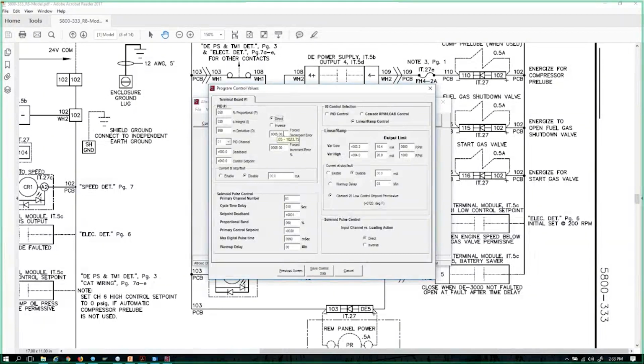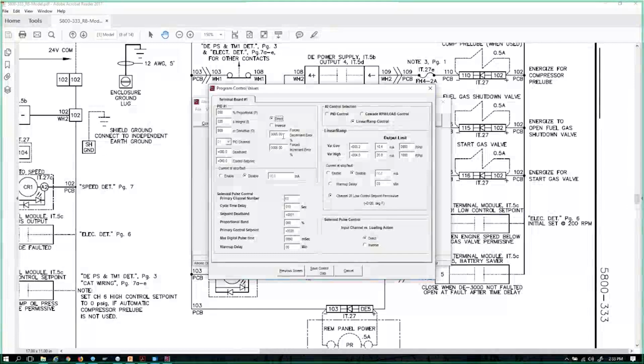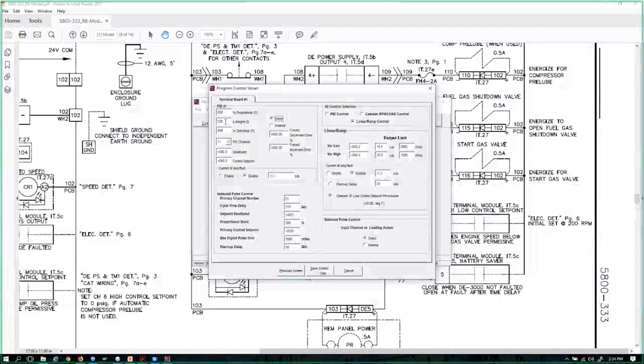I've been messing with the DE products since I think I got my hands on the very first DE product in about 2000, 2001. I've never changed these, never had a reason to. So 5% works good for me. But let's talk about proportional, integral, and derivative just a moment. So the default for proportional, if you're opening up a new software program, is going to be 120. Integral is 20, derivative is 999. Proportional is the biggest key.